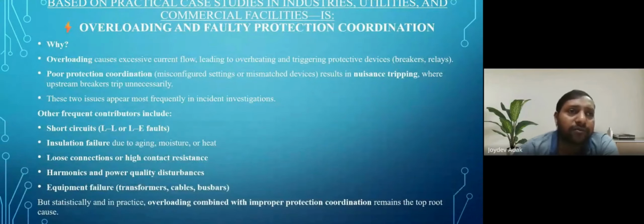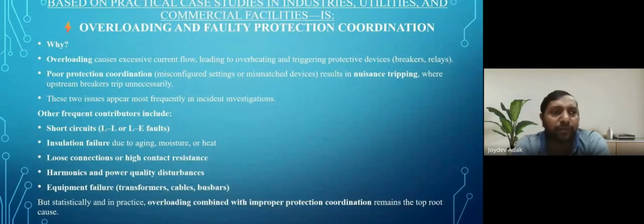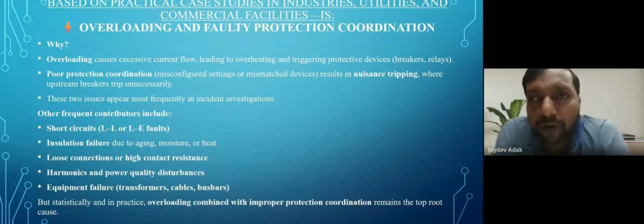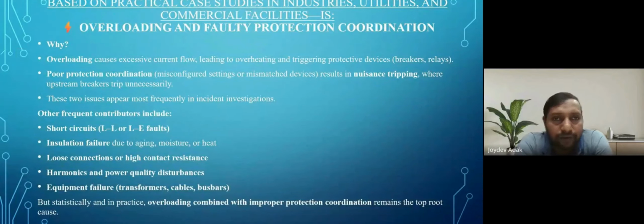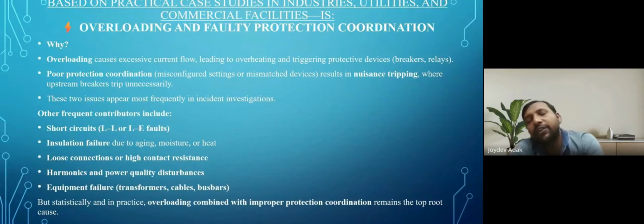Now, the common causes of major electrical system faults, coming to this point, are overloading and earth fault. This is the main cause. Overloading, that is overcurrent drawal by the consumer, is the main reason. Secondly, the earth fault, that is single line to earth fault. Another one is poor protection coordination. Other frequent contributors also include insulation failure due to aging problems.